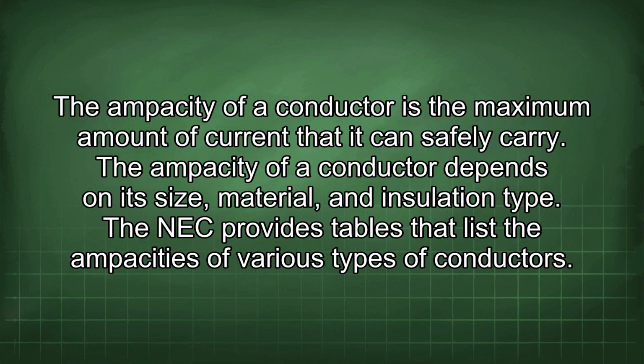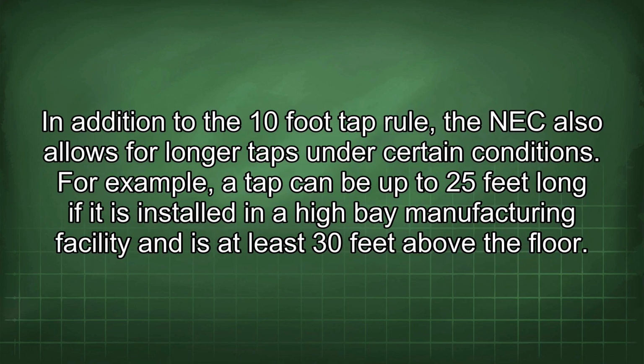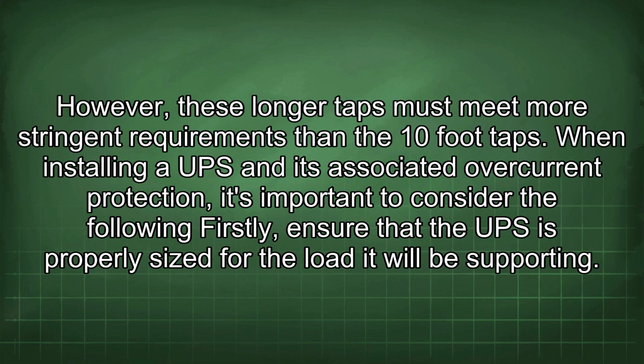The ampacity of a conductor depends on its size, material, and insulation type. The NEC provides tables that list the ampacities of various types of conductors. In addition to the 10-foot tap rule, the NEC also allows for longer taps under certain conditions. For example, a tap can be up to 25 feet long if it is installed in a high bay manufacturing facility and is at least 30 feet above the floor. However, these longer taps must meet more stringent requirements than the 10-foot taps.